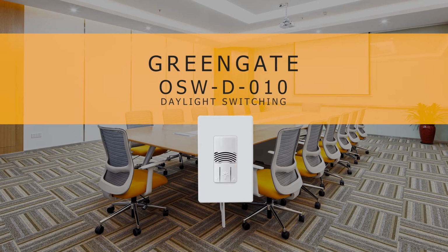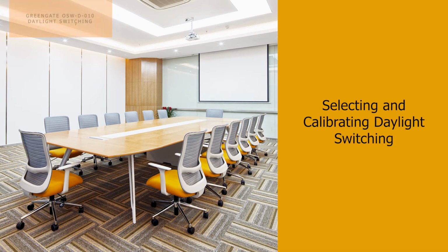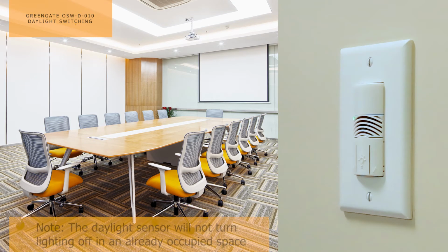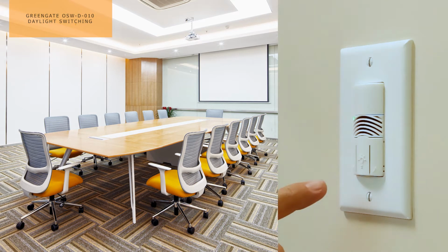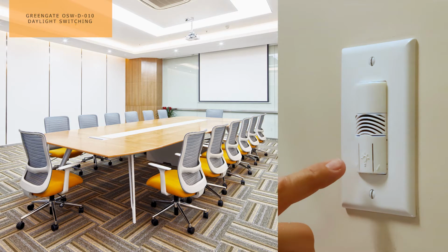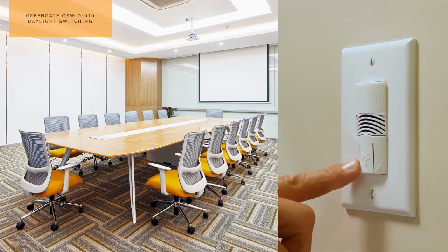This video is part of a series that explains how to configure different parameters for the 0 to 10 volt dual-tech sensor demo. In this video, we will demonstrate how to implement and calibrate the sensor's daylight switching feature. If daylight switching is enabled and the space is initially occupied, the sensor will not turn on the lights if there is adequate daylight. The occupant can use the manual buttons at any time to turn lighting on and off or to adjust the light level.